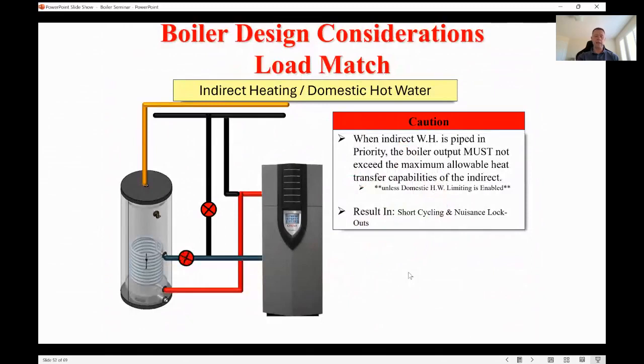Another thing you want to look at is the indirects, or if you're doing domestic with it as well. A lot of these can handle domestic through an indirect tank, which is basically a tank with a coil in it. There's two different options. You can do it as a zone, which is off your secondary or your system loop, and a lot of them will have it doing it off a priority. Now, for a house, a residential situation, you might be in a situation where your domestic load is higher than your heating load for that house. In that case, you're generally going to size your boiler for your domestic load, and you're going to hope that your modulation will handle the rest, so you don't get into cycling or overshooting issues with your heating load. Although it's not always like that.